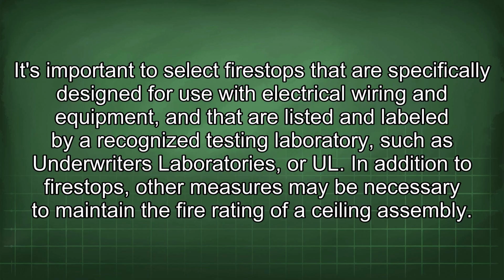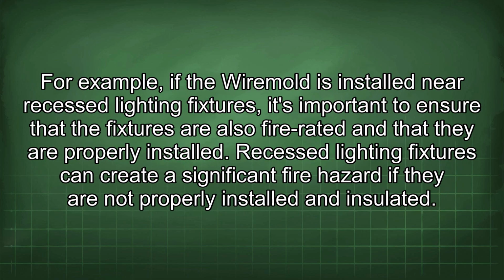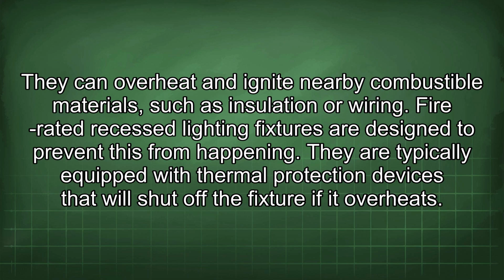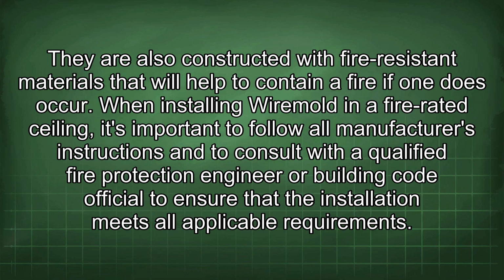In addition to fire stops, other measures may be necessary to maintain the fire rating of a ceiling assembly. For example, if the Wiremold is installed near recessed lighting fixtures, it's important to ensure that the fixtures are also fire-rated and that they are properly installed. Recessed lighting fixtures can create a significant fire hazard if they are not properly installed and insulated. They can overheat and ignite nearby combustible materials such as insulation or wiring. Fire-rated recessed lighting fixtures are designed to prevent this from happening. They are typically equipped with thermal protection devices that will shut off the fixture if it overheats. They are also constructed with fire-resistant materials that will help to contain a fire if one does occur.